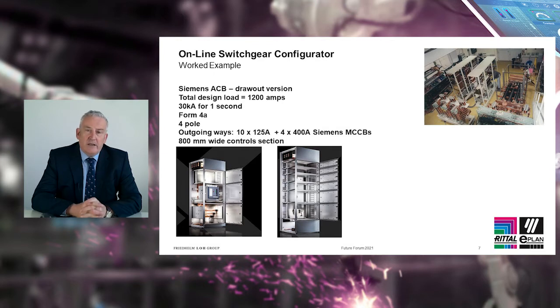The form rating is a segregation of the bus bars from the terminals and the compartments. The configurator again needs to know that it can do Form 2A up to Form 4B, so it has a full range of options. The key one is the number of outgoing ways. For this example, we've got ten 125 amp MCCBs and four 400 amp MCCBs. Again, they are Siemens.